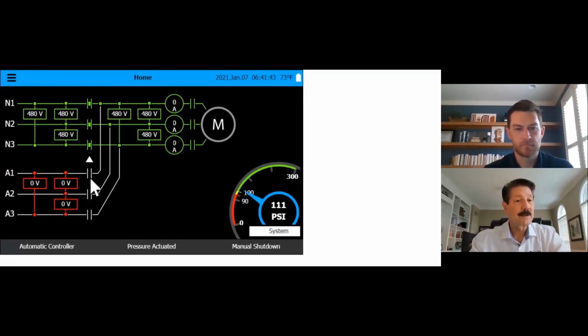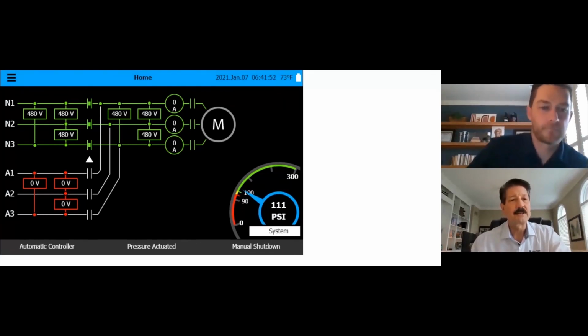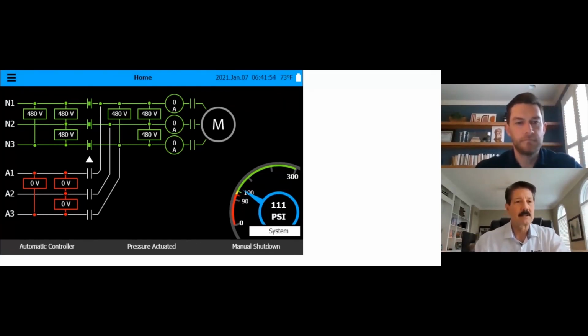And again, as you go to the right side of that, you see contactors that are open. And all this really, again, we could not have both of these energized and have both sets of contacts closed because obviously it would be a direct short. We can't do that. So the arrow in the middle here is pointing upward. And that is saying, hey, we're powering from the normal power. We'll show you as we progress through this that as we do a test for the genset, this will reverse and point to the bottom, and we'll just do a switch.